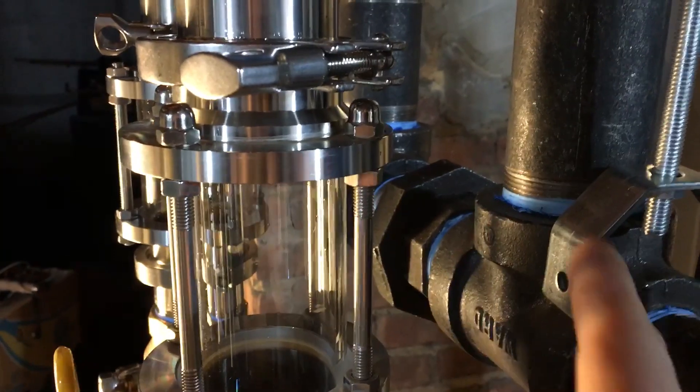And all that water - if any water is getting up over the peak here of the drop header down into the header, it's going to get caught by the edges of the interior of these pipes. And it's going to run along the bottom, then it's going to get captured and run back down into the boiler.